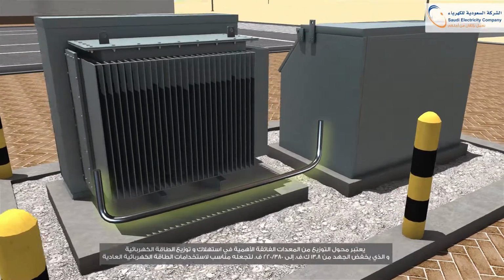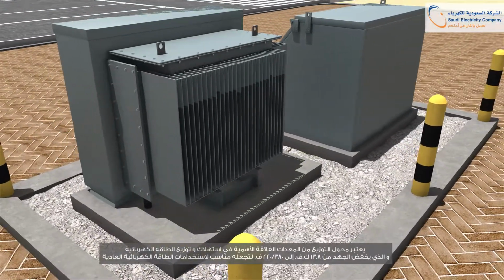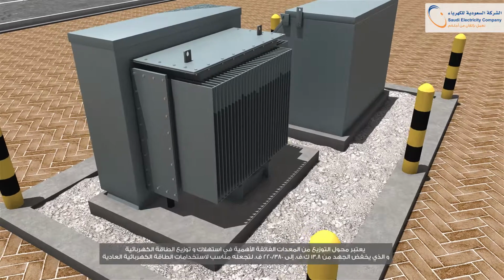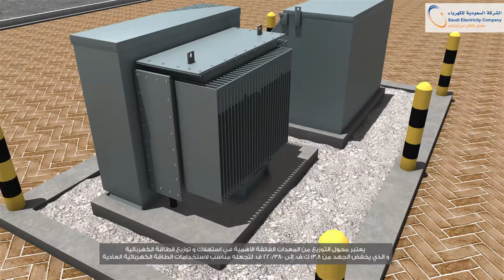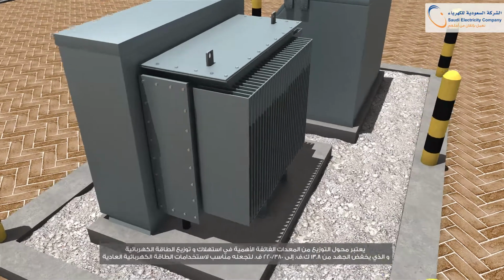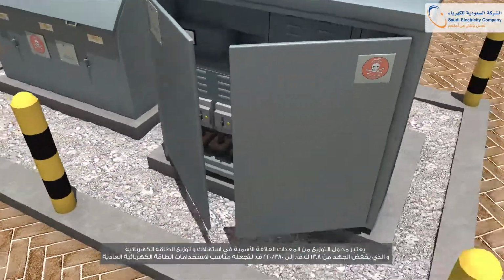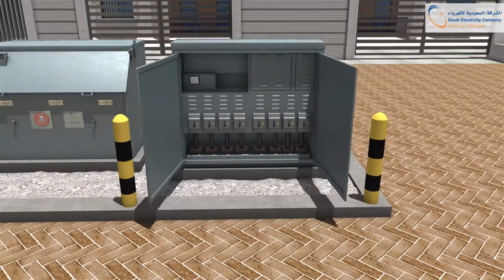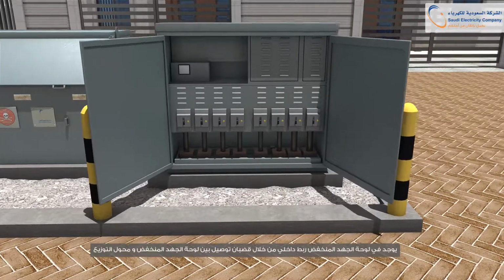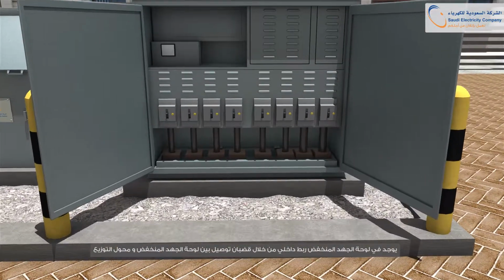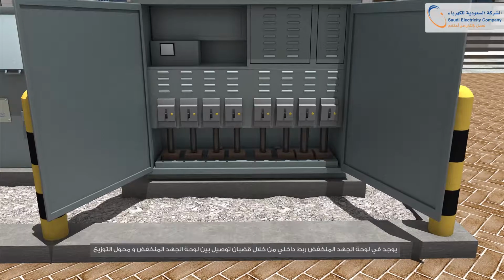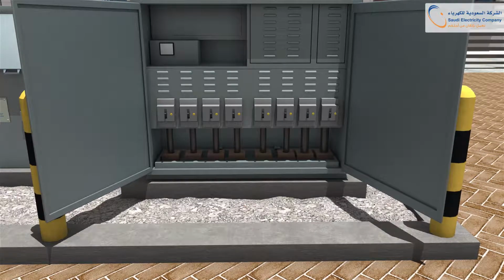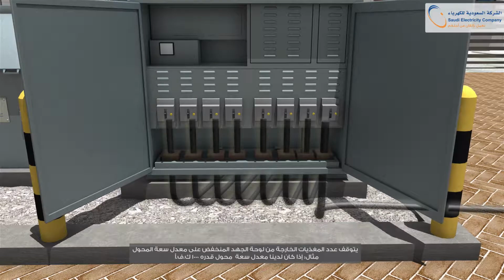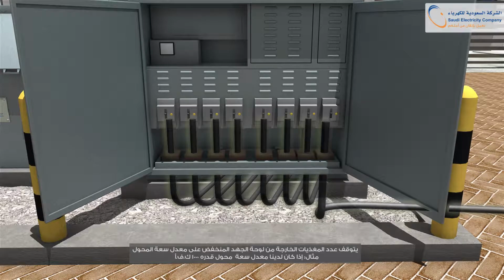The distribution transformer is considered highly important equipment for the distribution and consumption of electrical energy, which steps down the voltage from 13.8 kilovolts to 380/220 volts, to make it suitable for regular electric power uses. In the low voltage panel, there is an internal connection through bus bar between the distribution transformer and the LV panel. The number of LV panel outgoing feeders depends on the transformer rating.